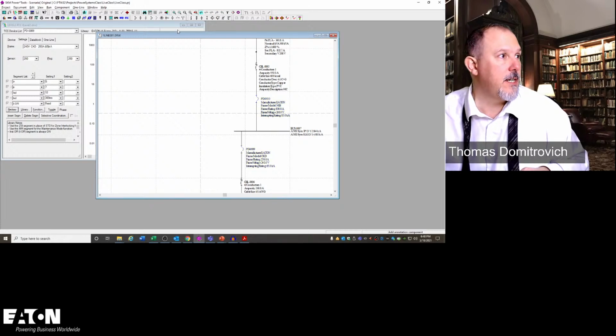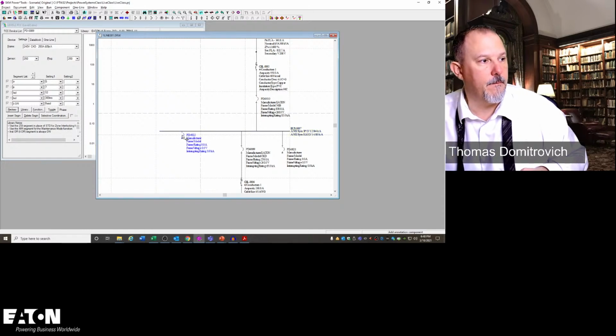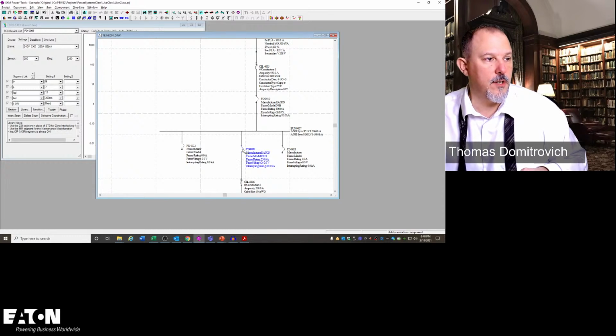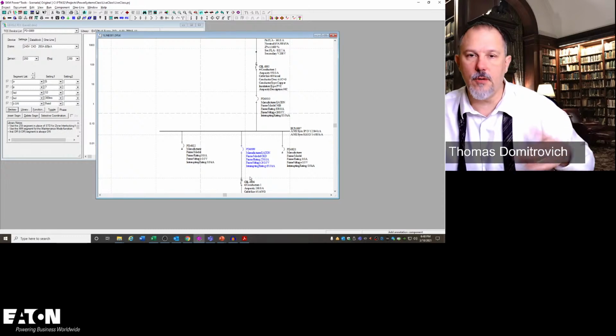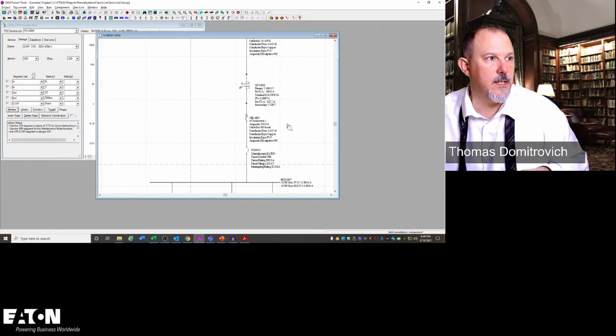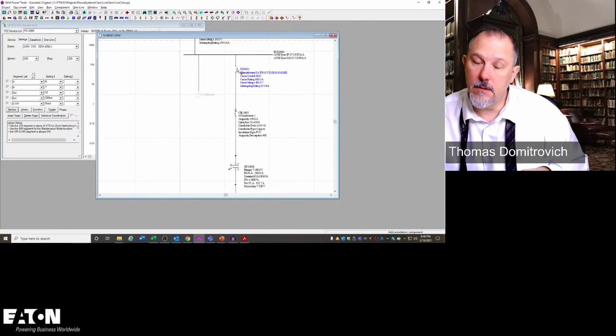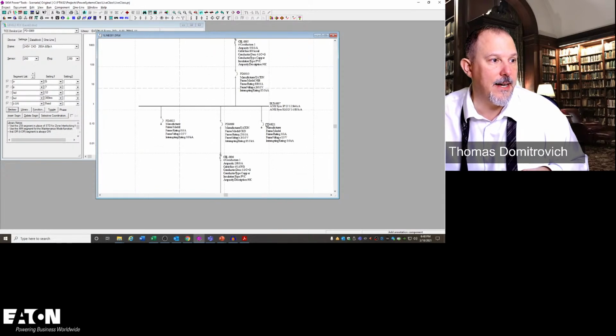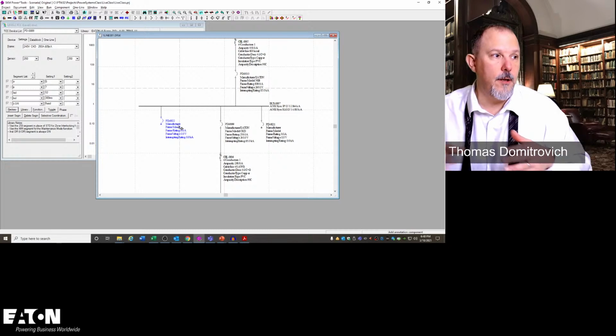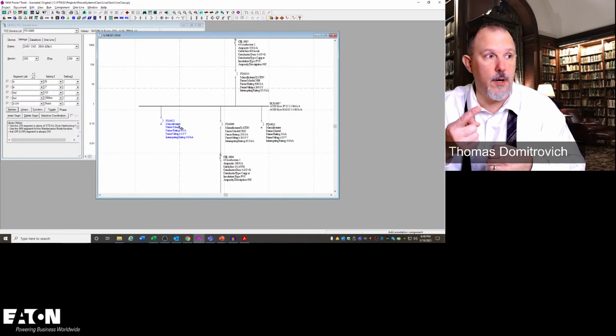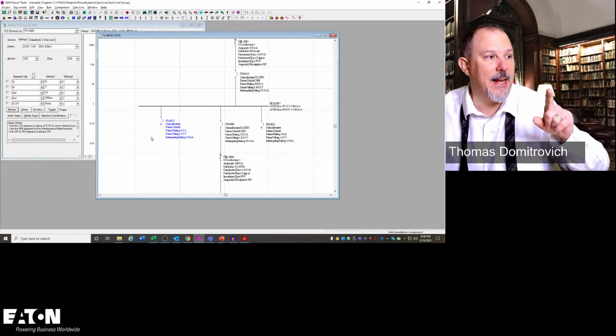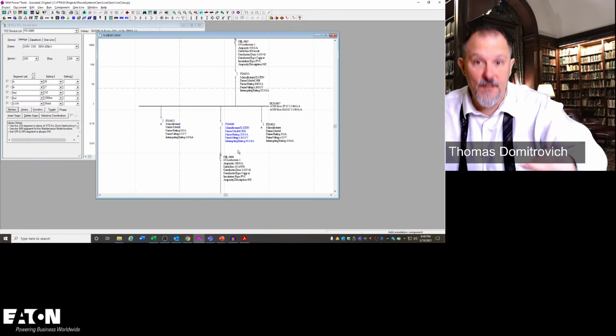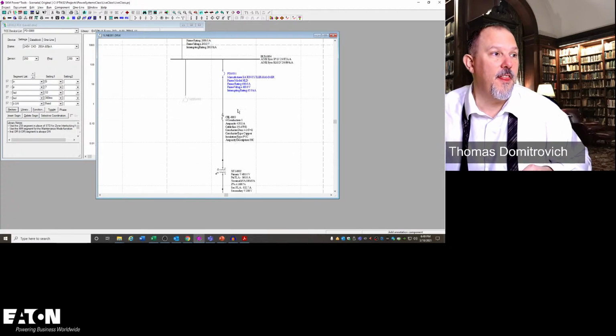I could throw this guy. I could do this. I could have this guy. If a fault downstream of PD9, say right at the load terminals, causes the main breaker to trip up here, then I take out the transformer and all of these other breakers. So you have to understand all of the breakers. Now, if there was just one breaker in that panel board, I could say you don't have to worry about it. But I have to selectively coordinate this 250 with that breaker.